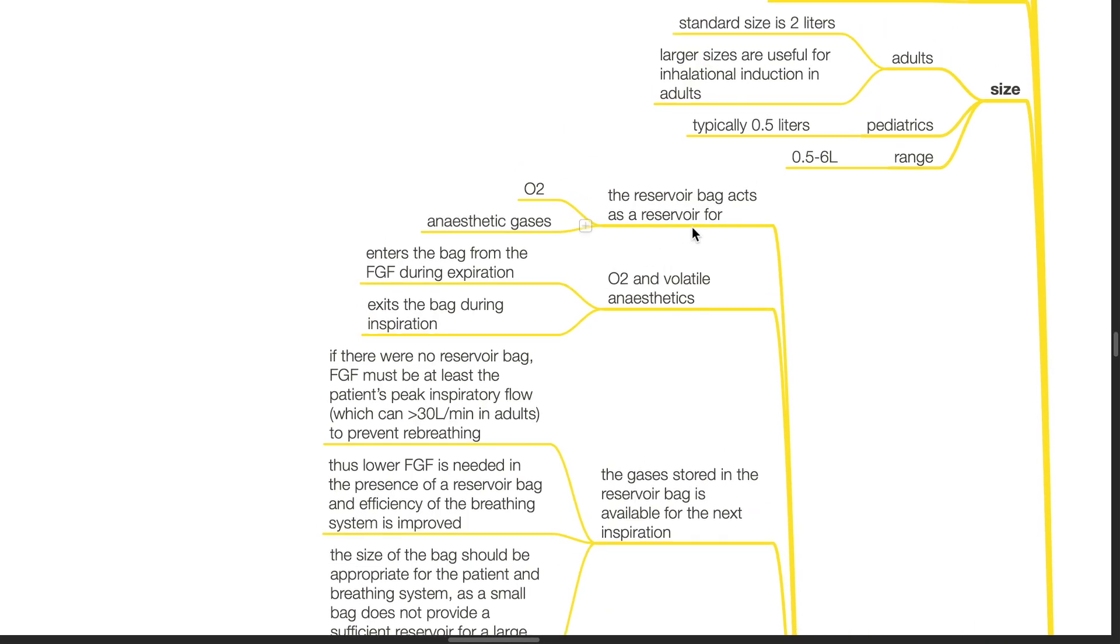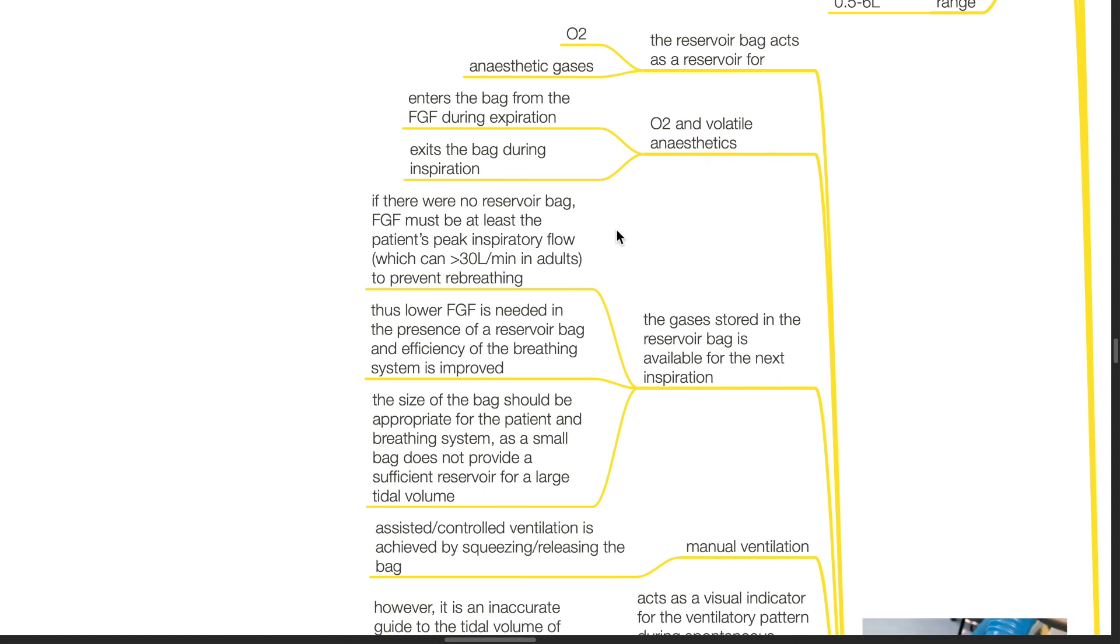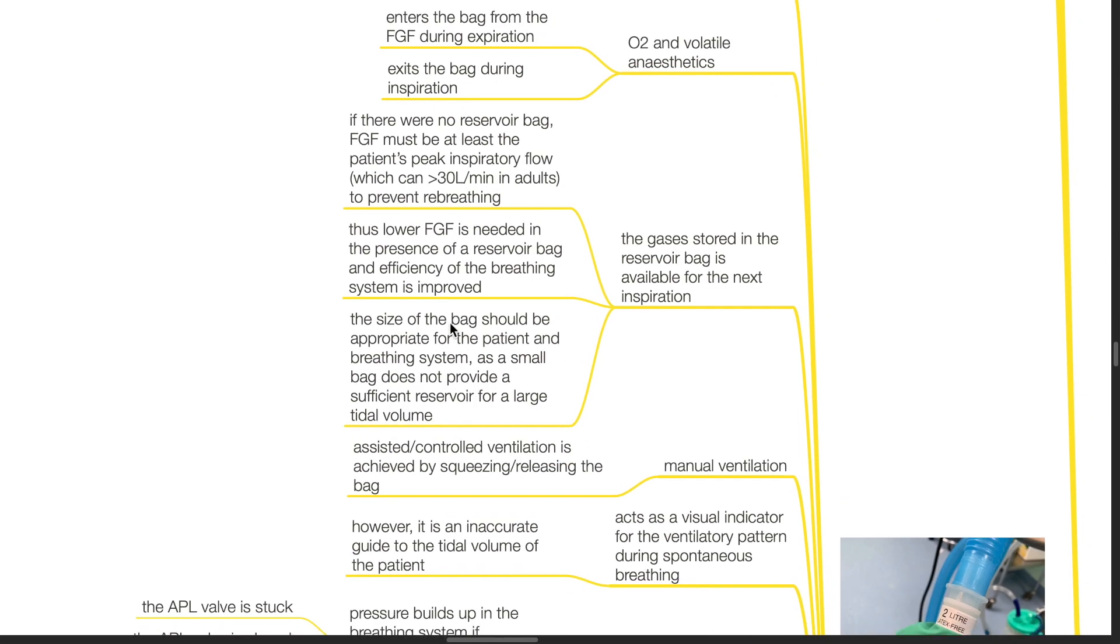Mechanism of action. The reservoir bag acts as a reservoir for oxygen and anesthetic gases. Oxygen and volatile anesthetics enter the bag from the fresh gas flow during expiration and exits the bag during inspiration. The gases stored in the reservoir bag is available for the next inspiration. If there were no reservoir bag, fresh gas flow must be at least the patient's peak inspiratory flow which can be more than 30 liters per minute in adults to prevent re-breathing. Thus, lower fresh gas flow is needed in the presence of a reservoir bag and efficiency of the breathing system is improved. The size of the bag should be appropriate for the patient and the breathing system as a small bag does not provide a sufficient reservoir for a large tidal volume.